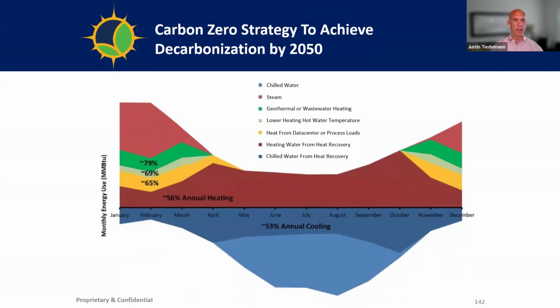So here is an example of what that might look like. A typical building load profile. You have your heating load and your cooling load. And you can see in this case, you're meeting 56% of your annual heating load just by capturing the rejected heat, or the heat that would have been rejected from your cooling system. And then there are some additional strategies you can layer on to reduce your peaks even further. Next slide.